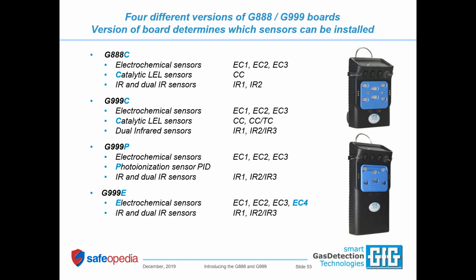With the 888, there's only one variant of the product—well, two variants. You have the same board, and it's your choice whether that board is wirelessly equipped or non-wireless. In all cases, it's your choice if you want to plug in a standard catalytic LEL sensor. It also supports your choice of IR sensors—single channel LEL, single channel CO2, or dual channel LEL/CO2—and it supports the complete range of available electrochemical sensors. It does not support PID; PID takes a lot of power, so your choice for PID is limited to the 999.